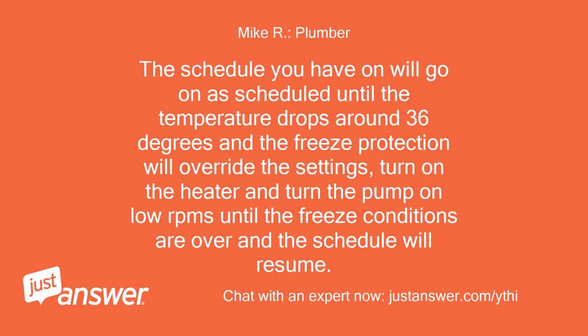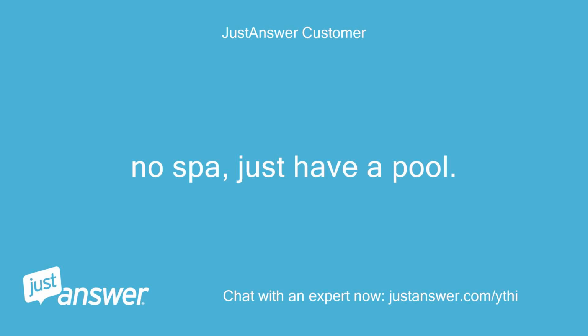The schedule you have on will go on as scheduled until the temperature drops around 36 degrees, and the freeze protection will override the settings, turn on the heater and turn the pump on low RPMs until the freeze conditions are over and the schedule will resume. No spa, just have a pool.